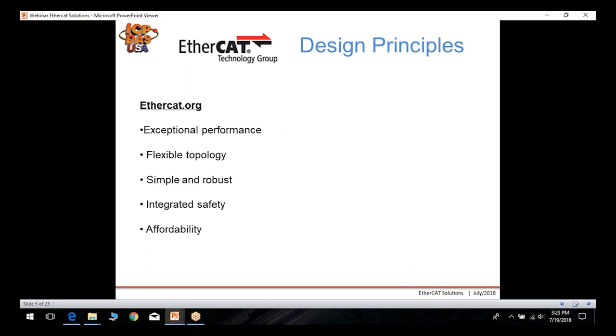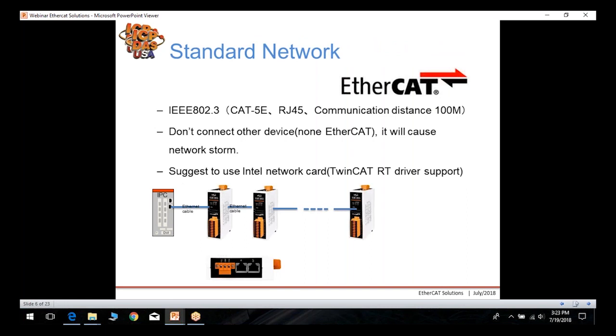The design principles of EtherCAT, as defined on the EtherCAT.org site, include exceptional performance, flexible topology, simplicity and robustness, integrated safety built-in, and affordability. EtherCAT uses a standard network defined by IEEE 802.3 using Category 5E RJ45 cabling with communication distance up to 100 meters between nodes.